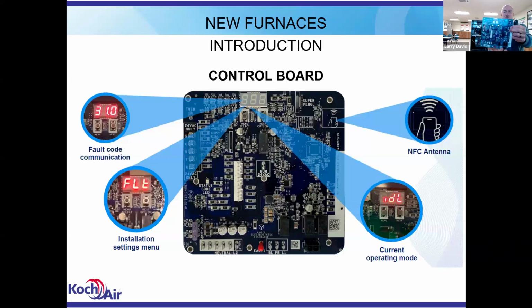All your line voltage connections are across the bottom. You can see the red plug over that EAC terminal. That's because anytime that fan's running, that terminal is energized and that's 110 volts going out. So to keep somebody from accidentally getting onto that, they've covered that.